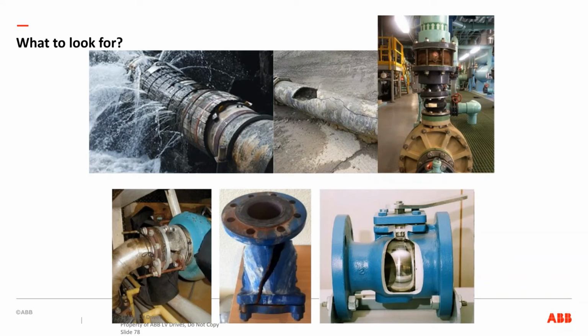And that's something that we're always looking for. We'll go into a plant and look for the pumps that are starting across the line and see if the motor mounts are broken or if they've had to be repaired or replaced. We also look for the valve fittings and the expansion joints and make sure those are still in line, because starting and stopping across the line does damage to those. Here we have a ball valve, and we have another valve here that actually has a crack in it from a water break. And the same thing here in this valve connection. Those are all things we want to look for.